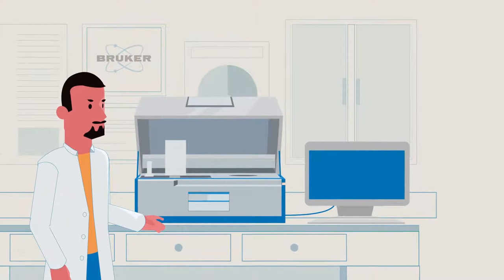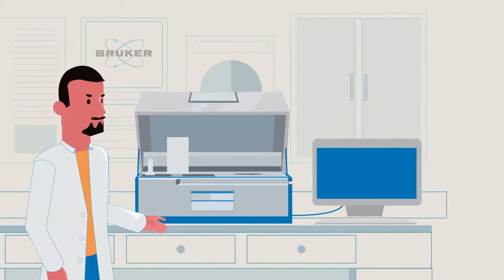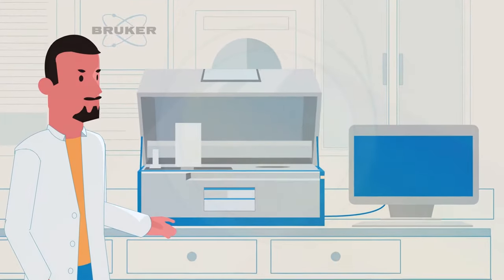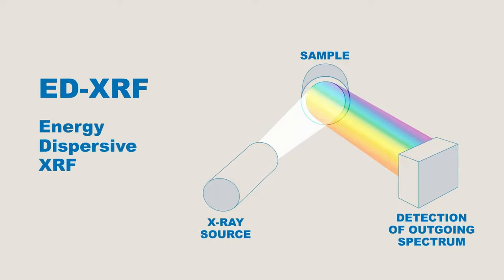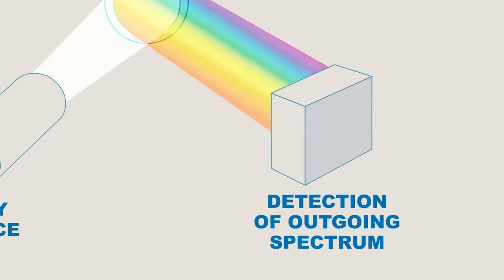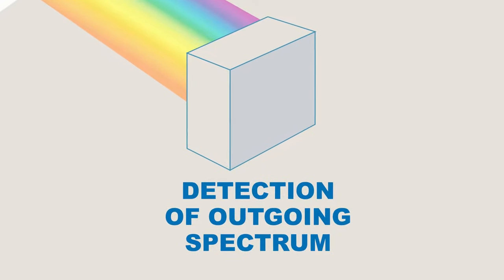Each element emits a unique fluorescence. There are two techniques used to separate and identify these energies. The first method is known as energy dispersive, or EDXRF. The spectral resolution in EDXRF is achieved by the quality of the detector. These detectors have several thousand channels to simultaneously measure the entire spectrum coming off the sample.